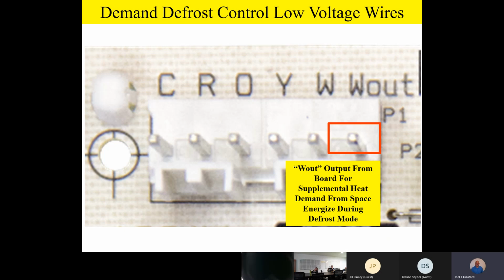But always remember, no matter what, whether you use that W circuit or not from the thermostat outside, please write this down, you always want to bring W out from the outdoor unit inside and hook it up to your auxiliary heat, because that's what's going to bring the auxiliary heat on during defrost. Because if you forget to bring that W out in and hook it up to your auxiliary heat, you're going to freeze the homeowner out every time it goes into defrost. So always bring that W out in for your auxiliary heat during defrost.